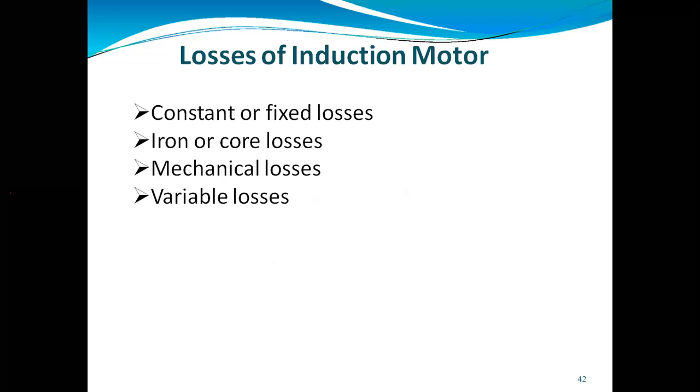If we are using silicon steel to make the core, you can say if we are using high grade silicon steel, you can minimize hysteresis loss, because the core losses depend upon the frequency, and the frequency of stator we are taking as the supply frequency, and the frequency of rotor is slip times the supply frequency, because you will get N_s equal to 120 F upon P. So we can say here the frequency of rotor is the slip times the supply frequency, which is always less than the stator frequency.